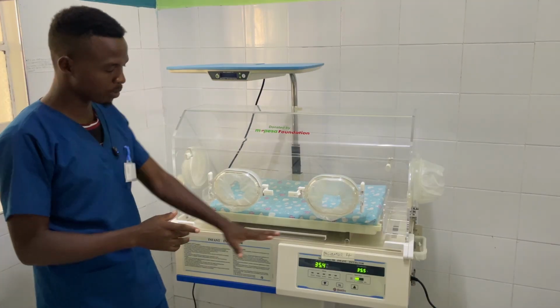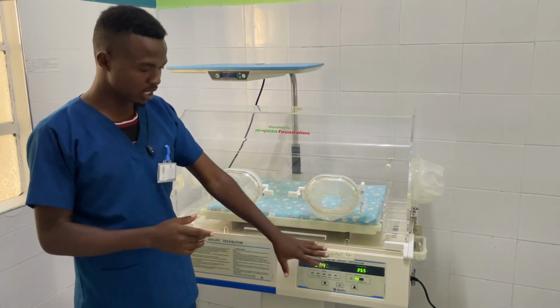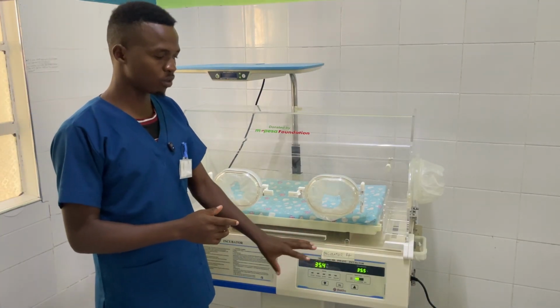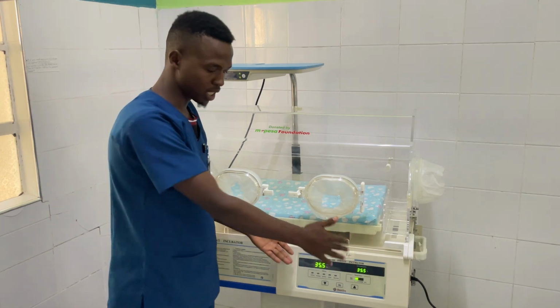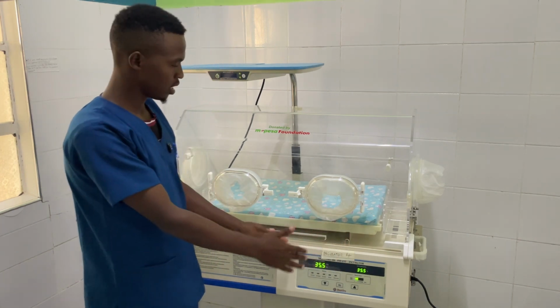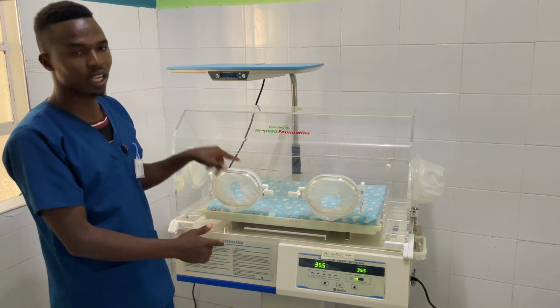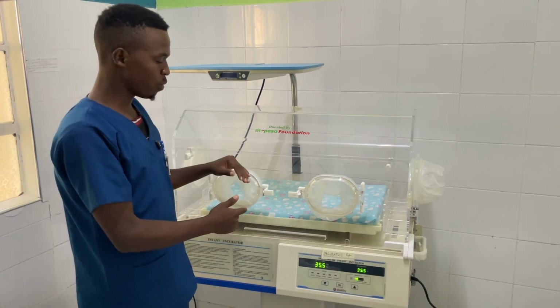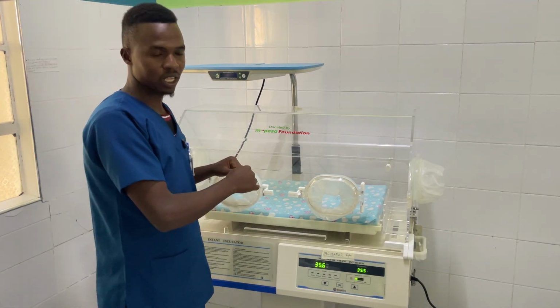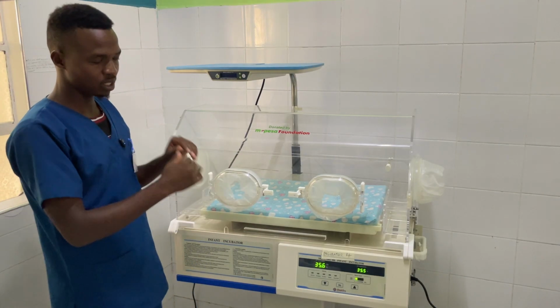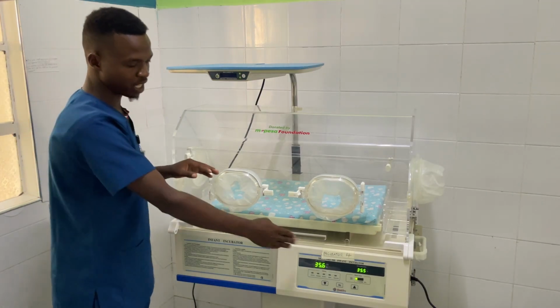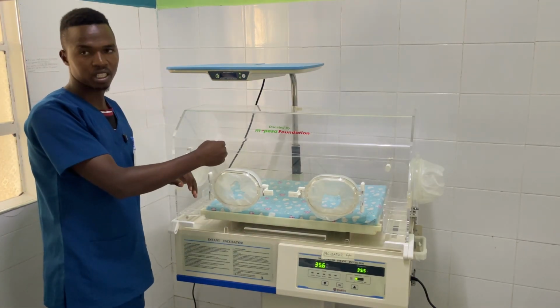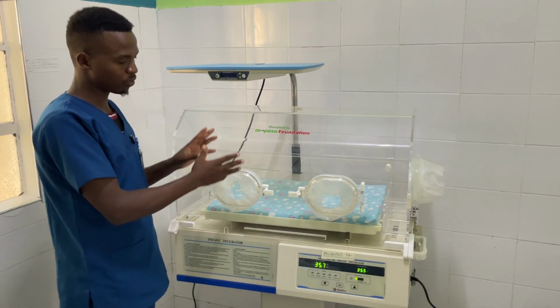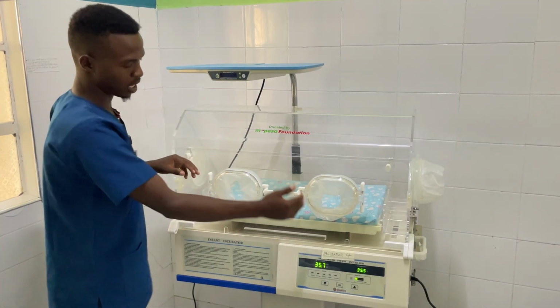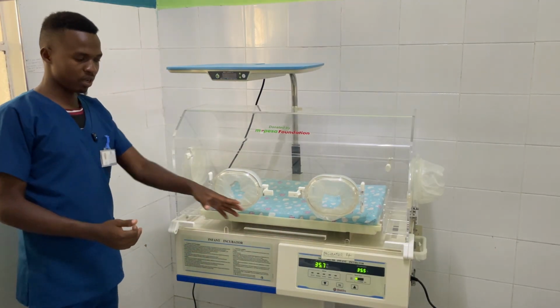The other one, we have talked about the settings. Make sure the settings are correct. Apart from checking that the temperature setting outside is correct, we also need to confirm with the thermometer the baby's temperature, because we have said machines can have a fault. It could be giving us a wrong reading, yet the baby's temperature inside is different. So you have to compare the baby's temperature inside with what the machine is reading.